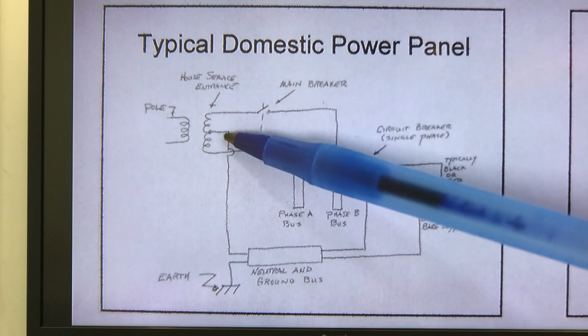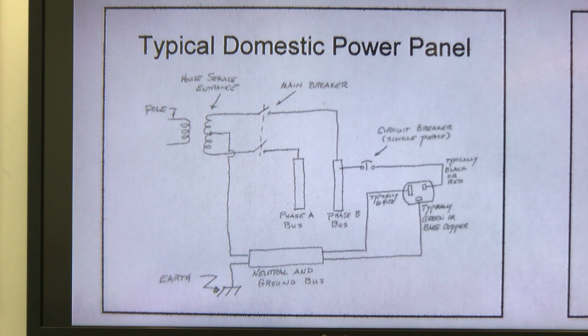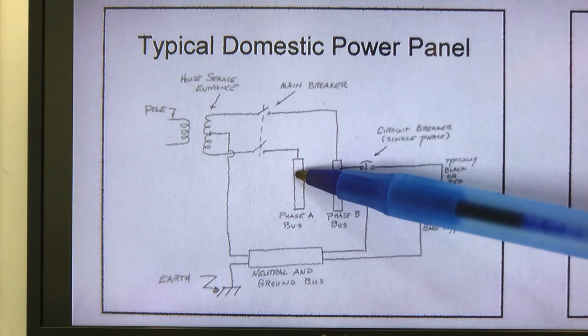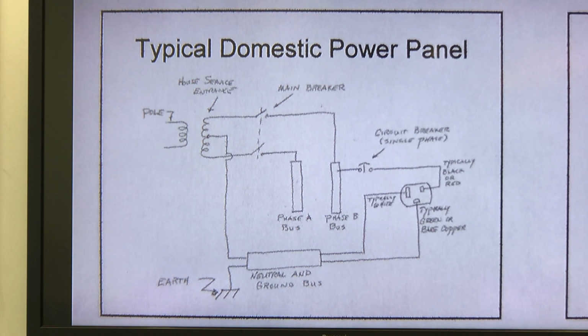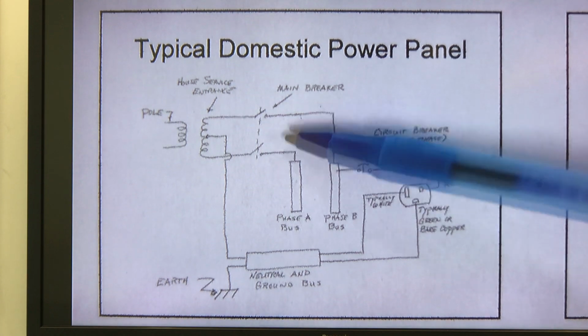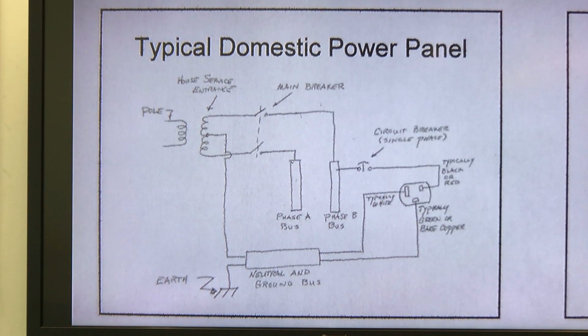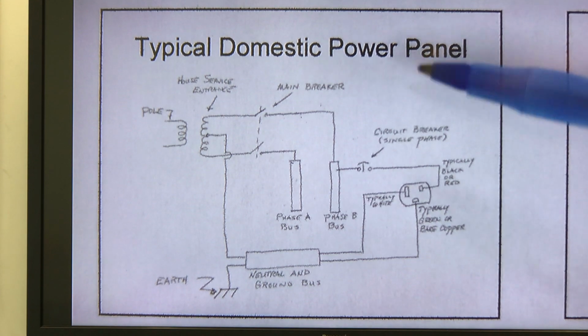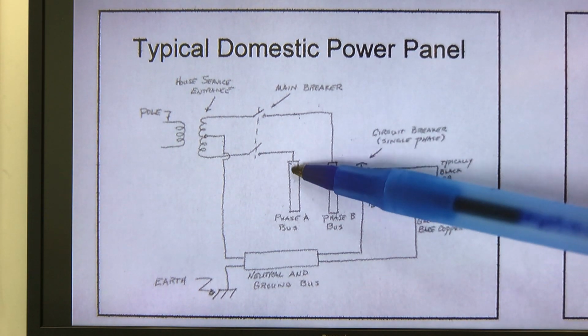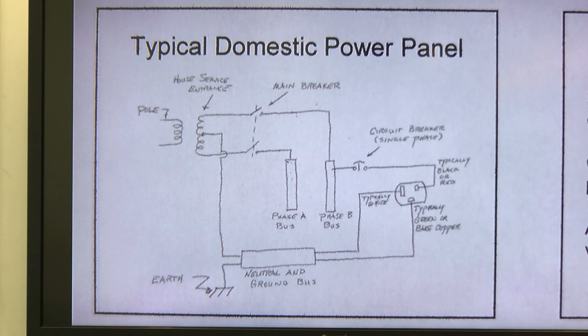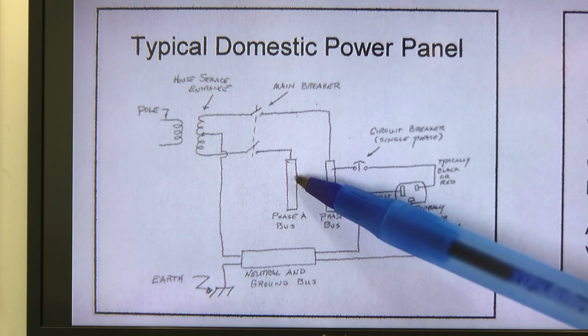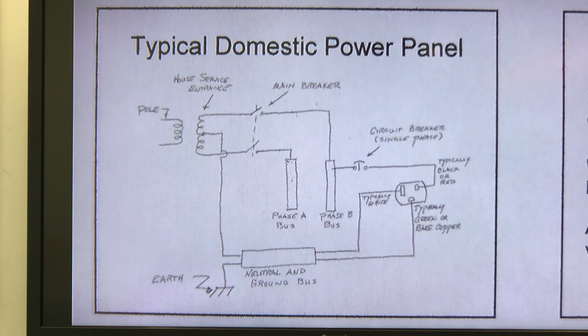In other words, this side, with respect to the center tap, is nominally 120 volts AC. Your other phase line, measured with respect to the neutral, is also 120 volts AC. Across the two of them, it's 240. So when you have power to your electric range or to an electric water heater, those typically, because their loads are heavy, span between both buses. But for normal operations, lights, typical plug-in appliances, typical portable loads, we need 120 volt power, and those can be connected to either the phase A bus or the phase B bus. It doesn't really matter which, because it'll look the same.